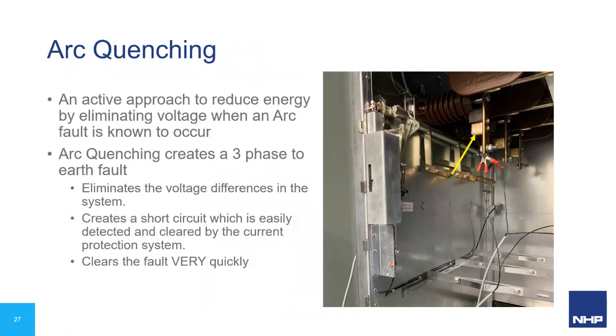The rest of our system in the high voltage world is a form of arc quenching, which has quite a few different variants out there, but effectively they all do the same thing. They create a three-phase to earth fault to replace the arc fault. Now, yes, that sounds mad, but it creates a very easily detectable fault for the overcurrent protection to pick up on and clear. The other thing it does, which is very important as well, is reduce all those voltages down to earth potential immediately. So it takes a lot of energy out of the system. This can help not only with the incident energy levels that you see in the switch room, but also with the cleanup that's involved. So instead of completely refurbishing something, it might be a clean up, retest, and off you go. So definitely some good potential there.